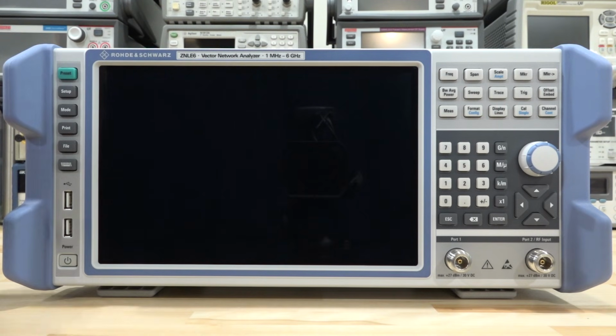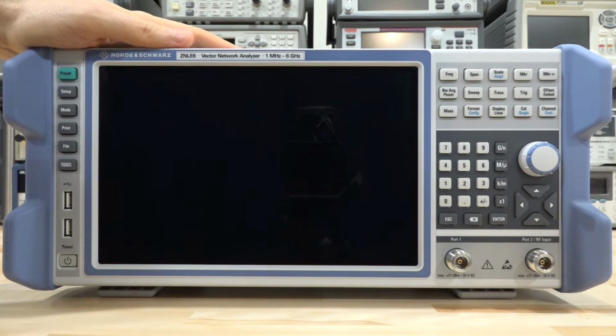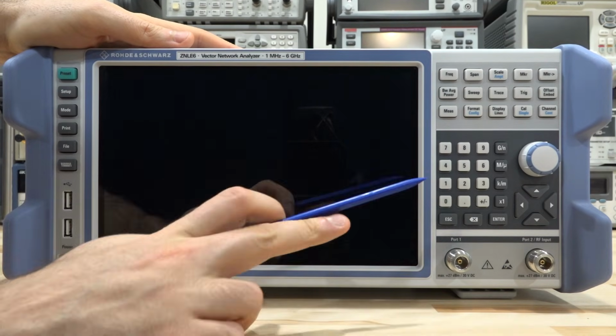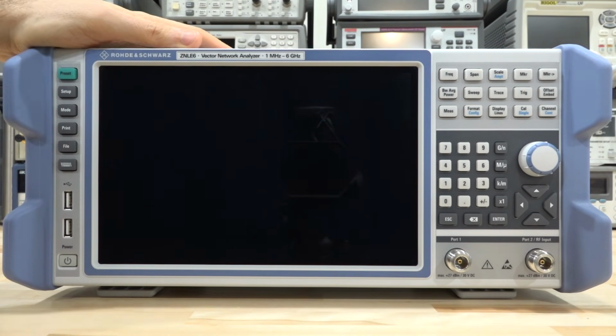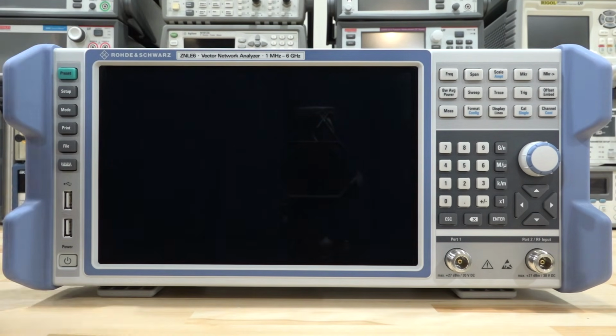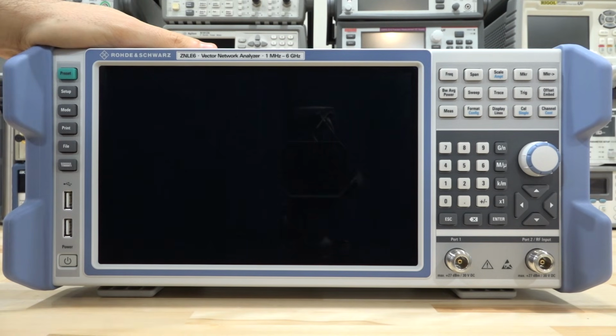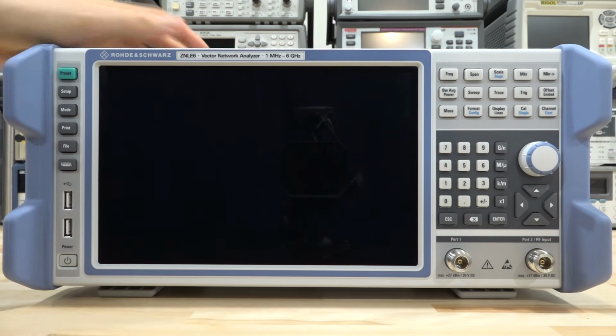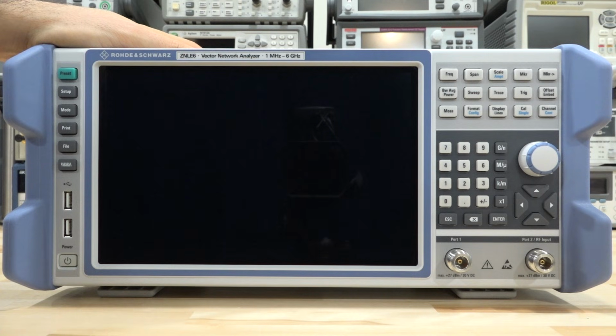It does have the front bumpers, which extend beyond the surface of the instrument. These are critical, especially for RF equipment, in case they fall or in case you need to rest them on the front. They extend beyond the RF connectors, the screen and the knob, so that it would protect them. This is great. And this is also used to mount the front cover in case you need to transport the unit. The front cover is a little bit difficult to get on and off the unit, but I would imagine that you don't have to do that all the time.